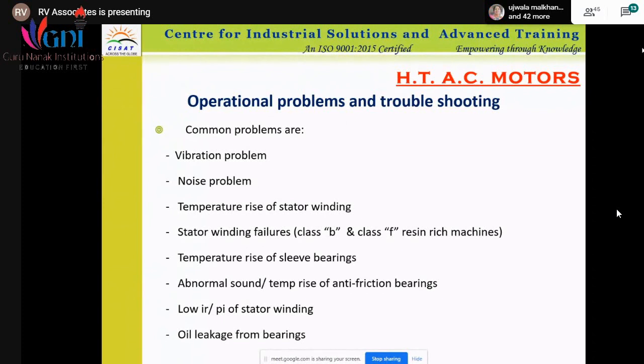There will be an oil tank, and that oil is circulated to the bearing to cool it. So it is possible that oil will leak from the bearing, which will lead to failure of the motor or a rise in temperature. So these are the problems for HT AC motors. Small motors are different. Industrial, bigger motors are different, because it's an electromechanical device. With a rise in temperature, you have to cool the system, so a cooling system is required.